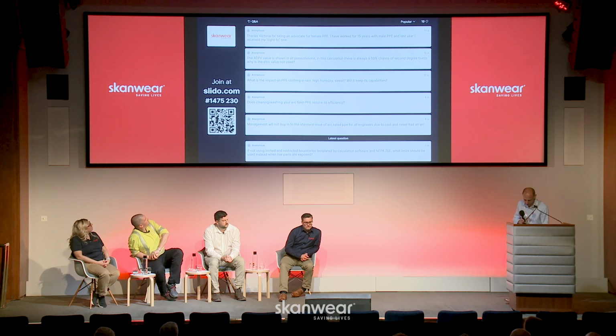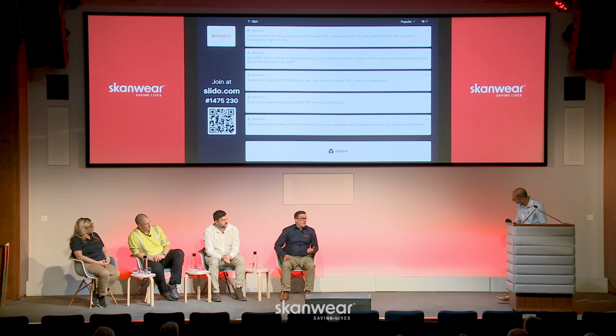ATPV value is shown on all presentations, and within that there's a calculation that it's a 50% chance of second-degree burns. Why don't we use the elimination value rather than that 50% value? When incident energy is calculated, it's an incident energy at a given distance from the switchgear. That incident energy isn't ATPV, it isn't EBT, it isn't ELIM, it's just incident energy. PPE is then rated in either ATPV, arc thermal performance value, EBT, energy breakthrough threshold, or ELIM, elimination. Originally, open arc testing was done in the USA on an open arc circuit, and the testing always gave two results, either EBT or ATPV. You have to advertise the lowest of those two ratings, okay?